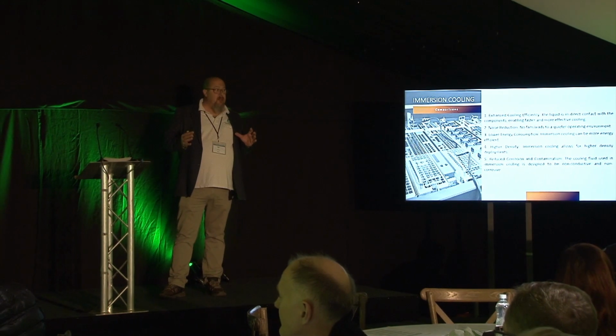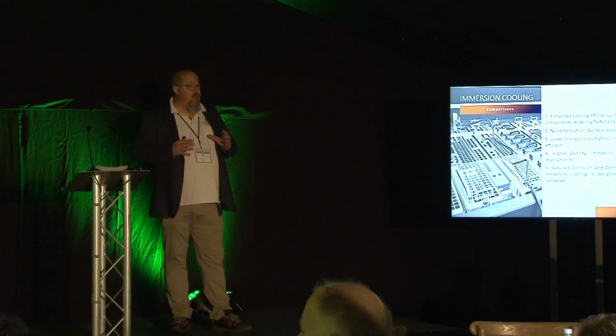But one of the best things about it is we can increase the density. Because we've got 10 times the capacity of heat in the liquid, we can actually run things more dense. And the best thing about it all is less contamination, less corrosion. You don't have problems with dust. You've got no mechanical parts on there, so therefore you're not going to get bearing wear or anything like that. We can compare them, the two methods, water versus oil-based cooling. Immersion-based cooling offers better heat dissipation, which is quite key. The installation of water and also immersion cooling are both complex, but it's different complexities.